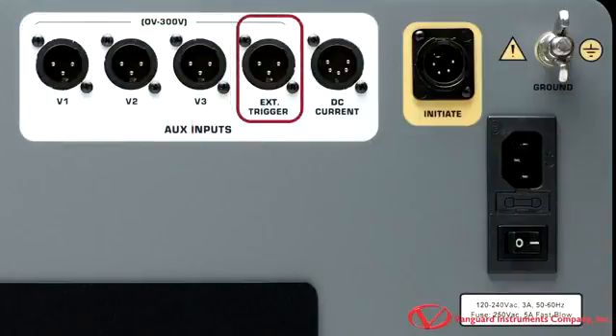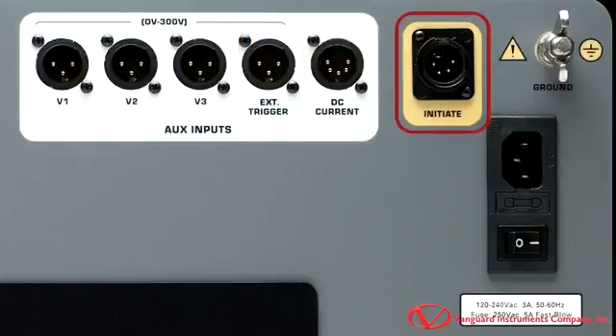The CT7000S3's external trigger input can automatically start timing with the detection of a voltage, and the initiate circuit energizes the circuit breaker's open or closed coil.